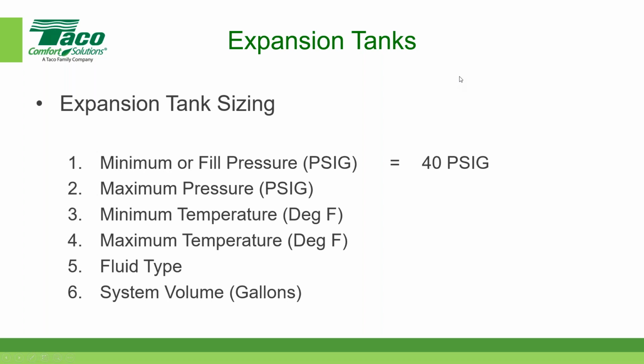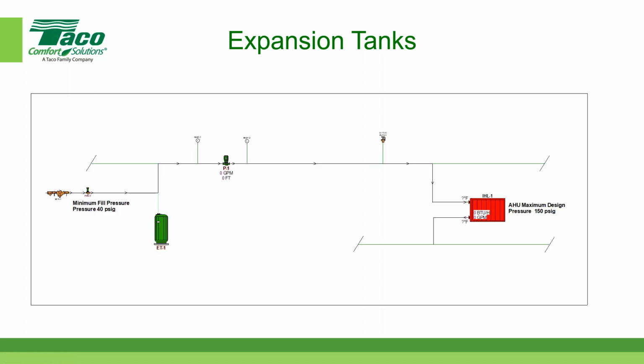They go a little faster as we go along here. What's the maximum pressure? Well, here's one method. It's not the only one, but here's one method that we can use to establish the maximum pressure. We've got a piece of equipment at the same elevation of all the other piping at the lowest part of the building. And this piece of equipment wants to see a maximum pressure of 150 PSIG.